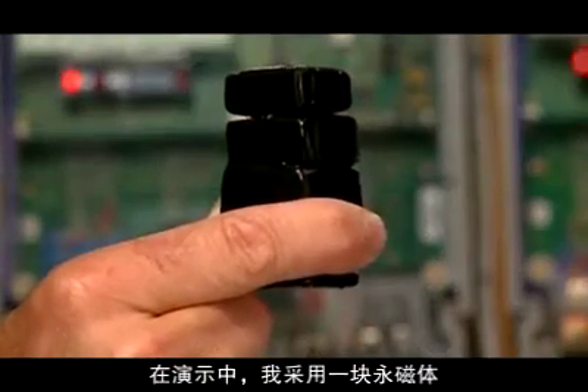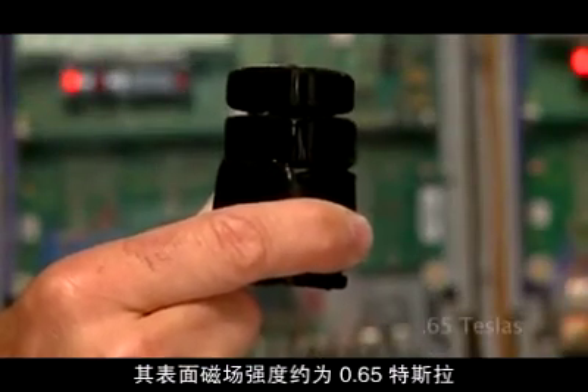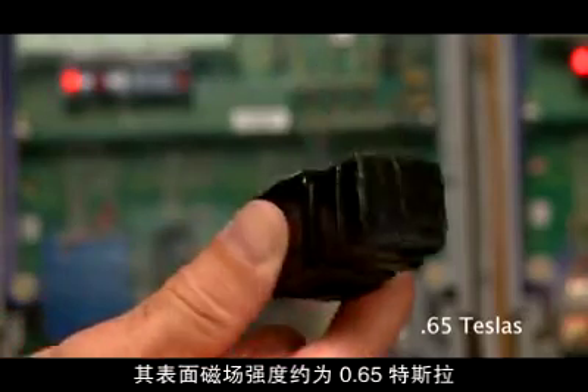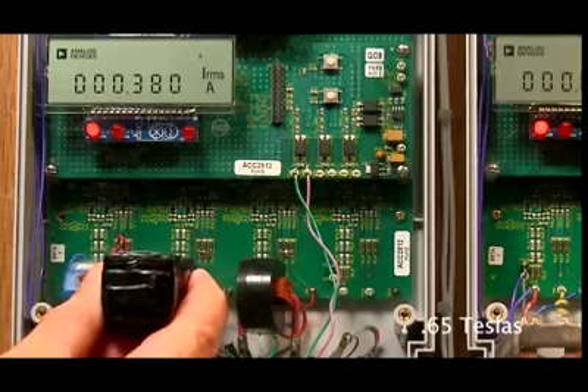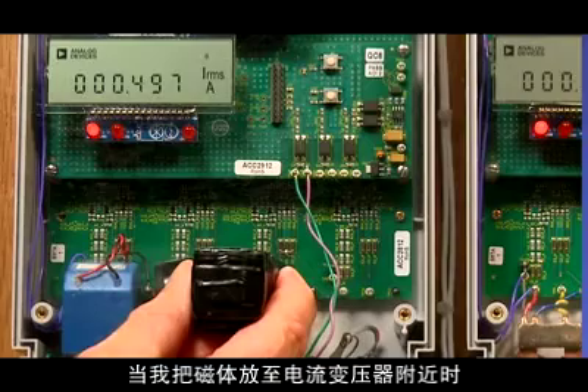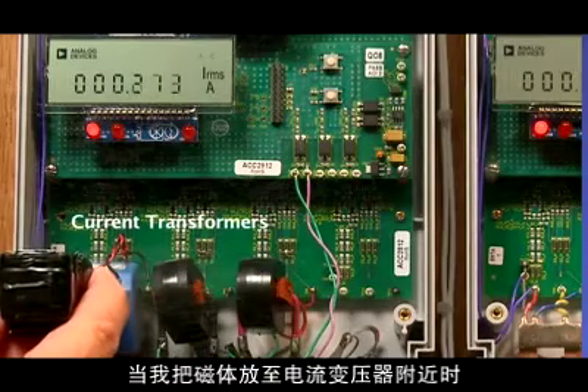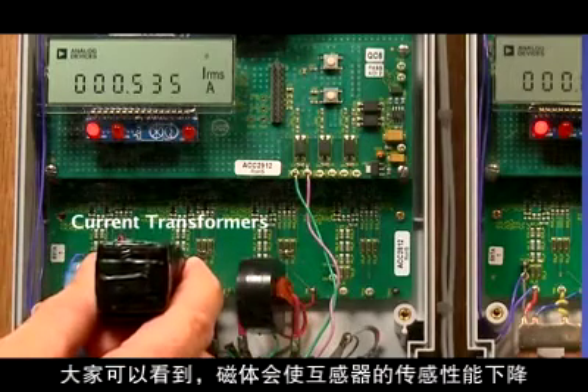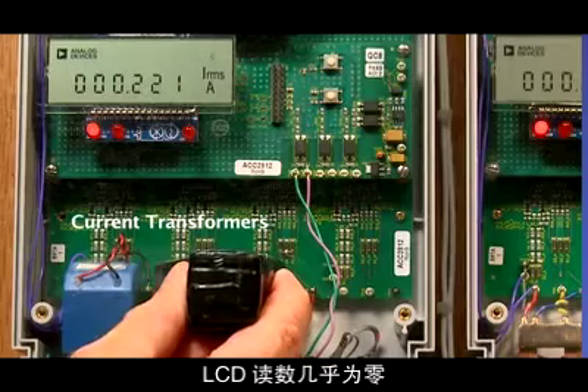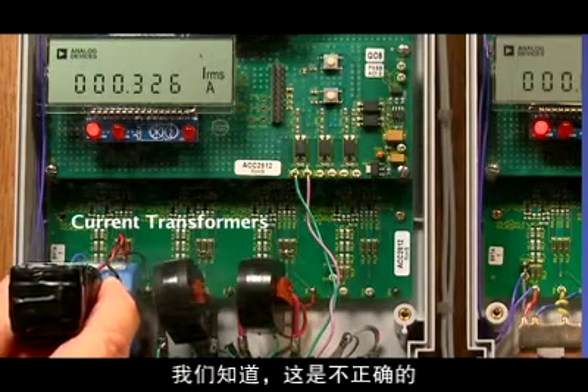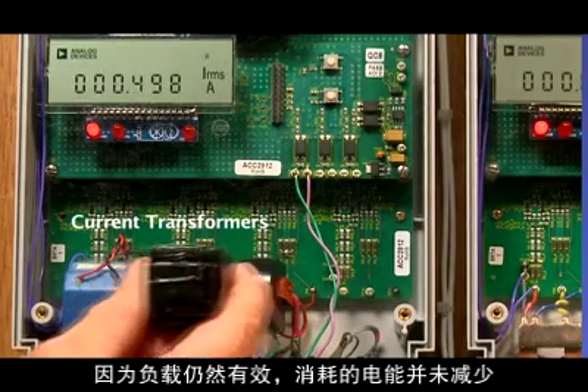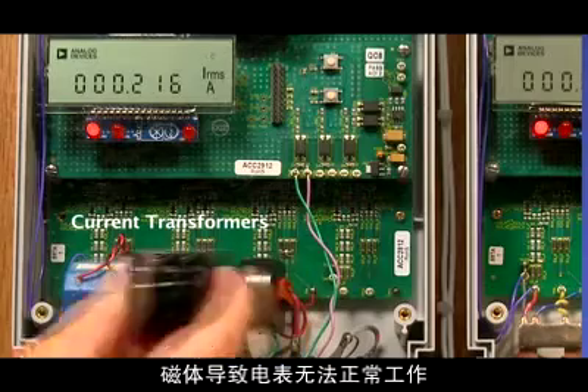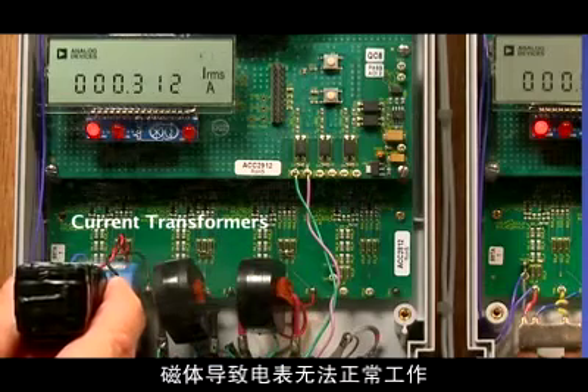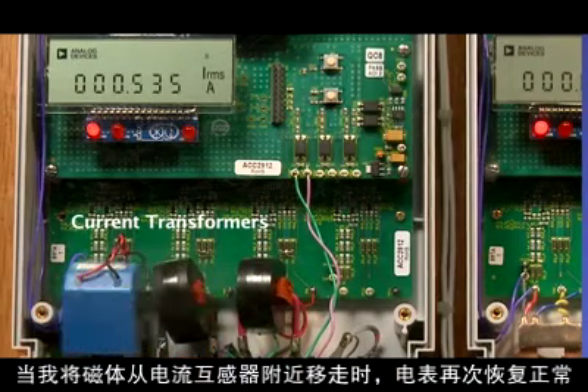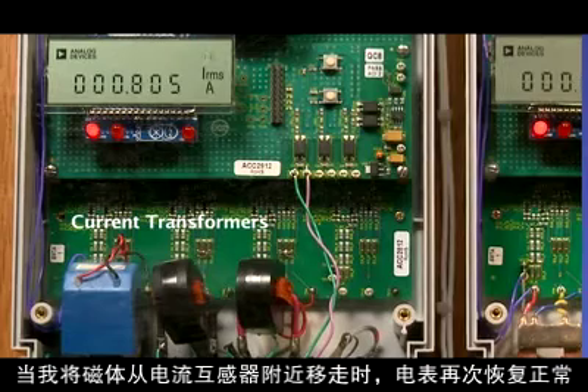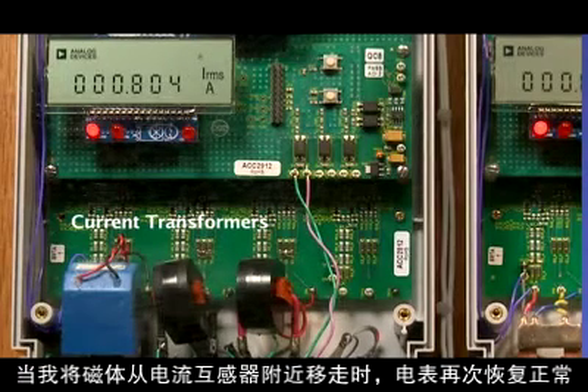For the demonstration, I'm using a permanent magnet with a surface field strength of about 0.65 Teslas. When I place my magnet in close proximity to the current transformers, you can see it degrades its sensing properties and the LCD readout is almost 0, which we know is not correct since the load is still active and consuming the same amount of energy. The magnet is causing the meter to stop working properly. When I remove the magnet from close proximity to the CT, the meter functions correctly again.